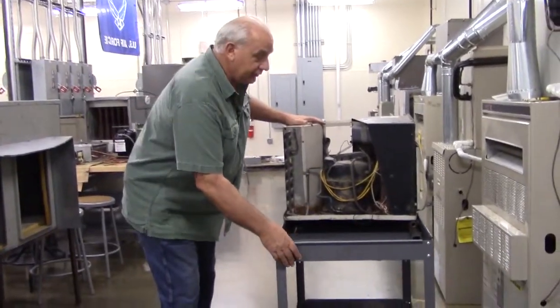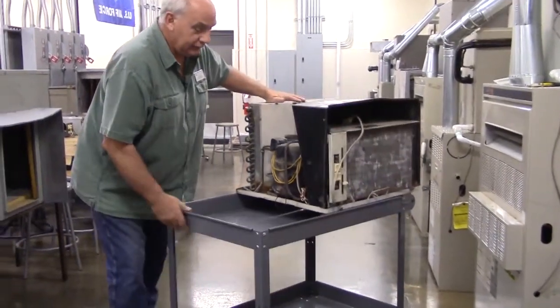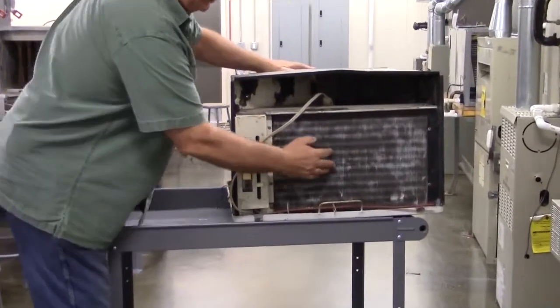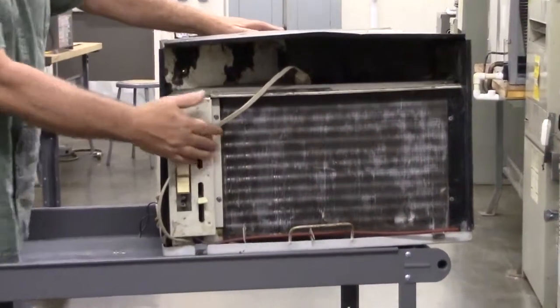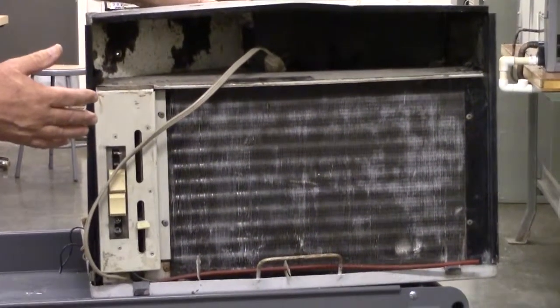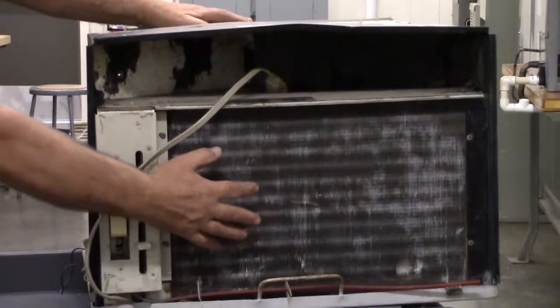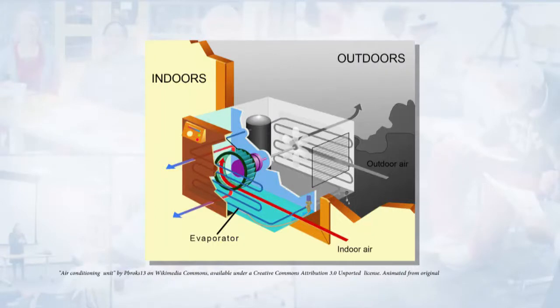The evaporator is this coil here. This would be on the inside of the room we want to condition and the air is drawn in across this evaporator. The refrigerant is boiling inside that evaporator and that absorbs the heat out of the air into the evaporator and into the refrigerant.